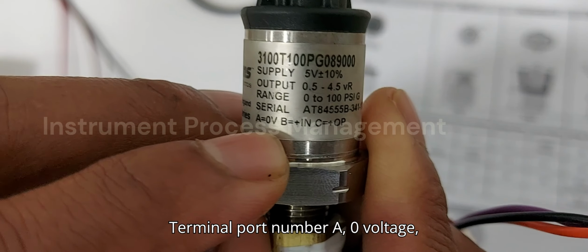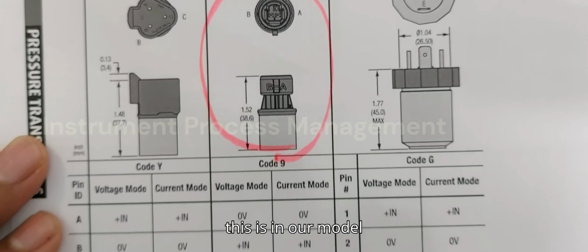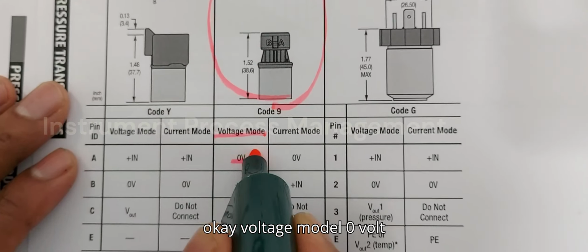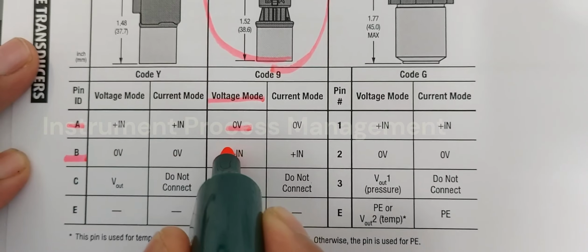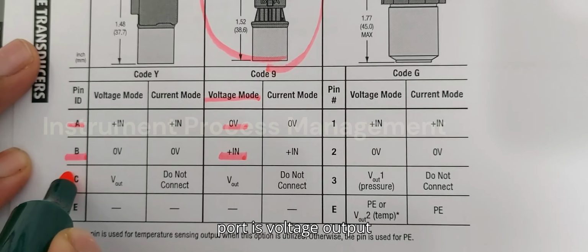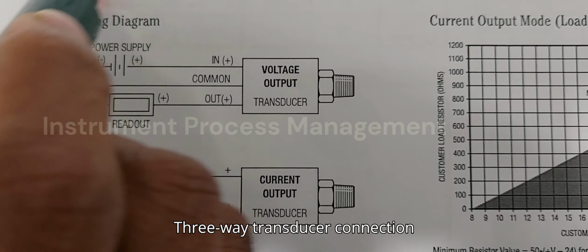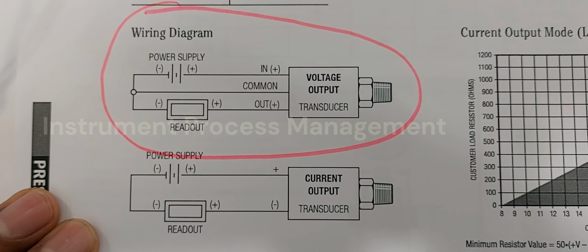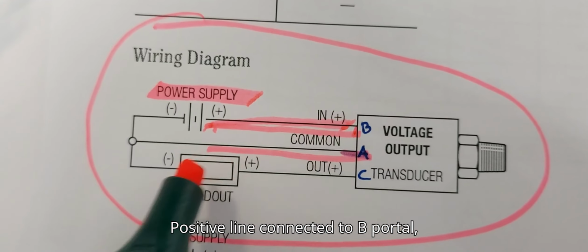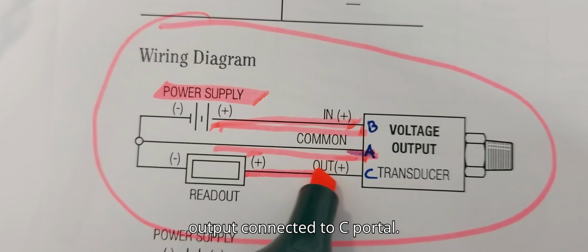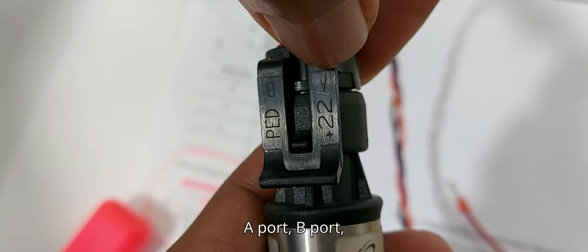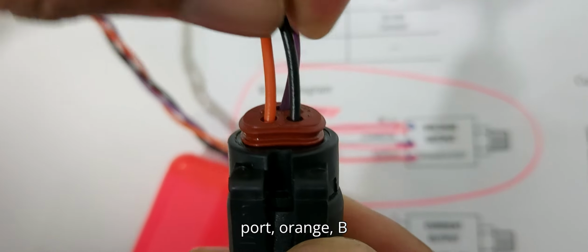Terminal port number: A is 0 volt, B is positive line, C is output line. This is in our model. Voltage mode 0 volt, that is A port, and the B port is positive line, then C port is voltage output. 3-way transducer connection by diagram. Positive line connected to B port, negative line connected to common port, output connected to C port. A port, B port, this is C line, C port, output. The wire color code: black A port, orange B port, violet color C port.